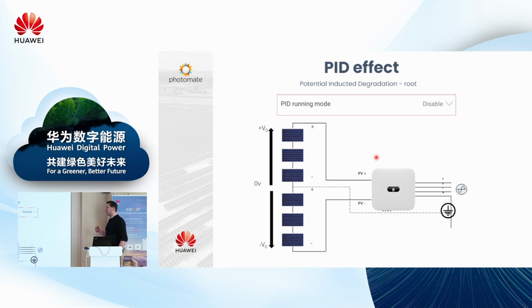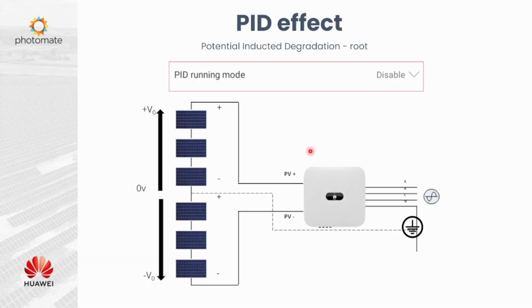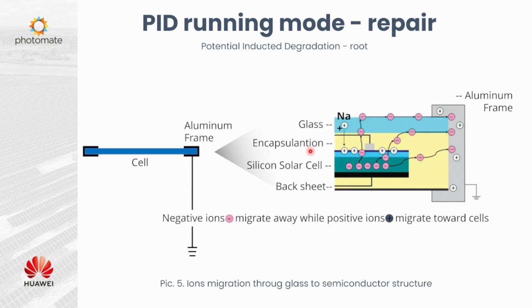I will stop here for a moment regarding the PID function. This is what wasn't told about the product itself, but it has an additional advantage, which is the PID recovery module. Let me explain shortly what the PID effect is. Right now, if we have transformerless systems, we always have a positive voltage comparing to the ground on the positive pole of the PV, and negative voltage comparing to the ground on the negative pole. So this difference of potentials might cause some ions from the glass to go inside the semiconductor structure on the PV module and contaminate it.